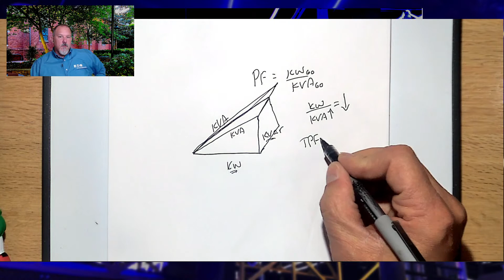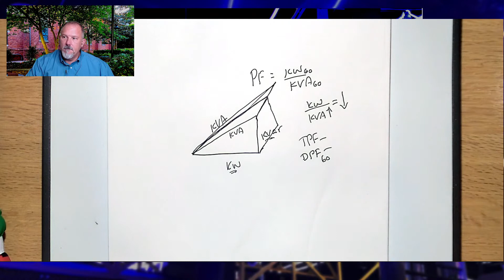What utilities bill for on commercial and industrial systems is called DPF, displacement power factor, and that's just 60 hertz. You know why? You came out of the metering group, Tom, so you probably remember when digital meters came out and suddenly you could measure all kinds of stuff, and people got excited. You could measure this power factor or that power factor—but the old meters used to just measure the 60 hertz one.